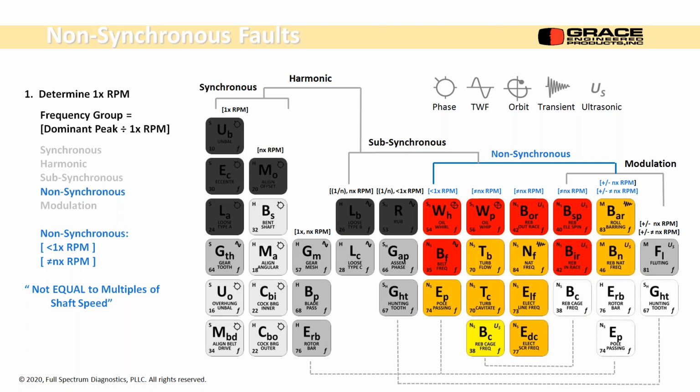And so how can that be? There's so many different kinds of bearings. I had a bearing database that had 18,000 bearings in it, and there were 3 that were exact harmonics. But you just take it out enough decimal places and it's going to be non-synchronous sooner or later. Anyway, so we have several different non-synchronous peak sources.